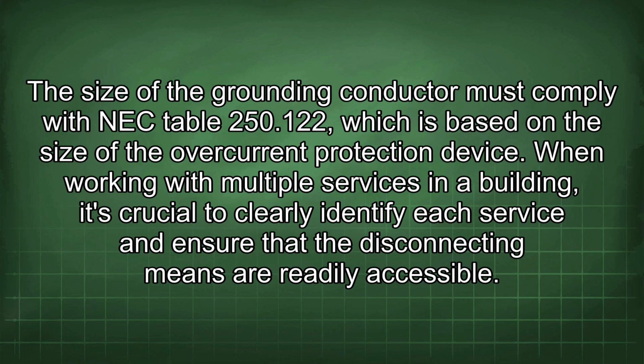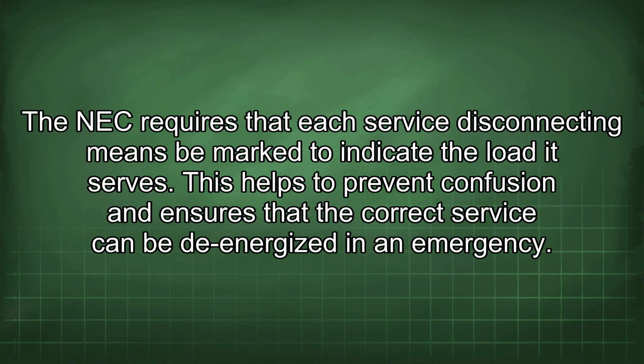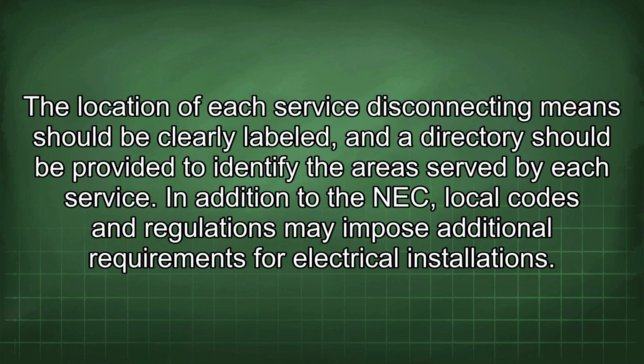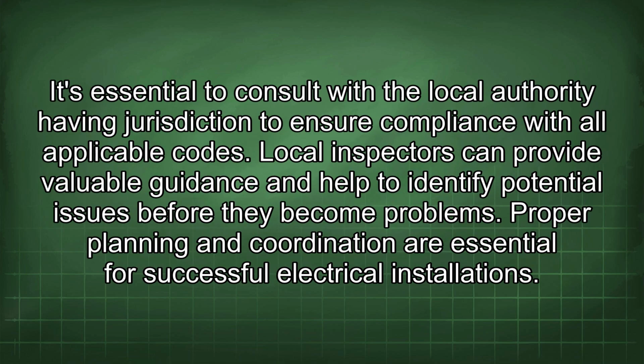When working with multiple services in a building, it's crucial to clearly identify each service and ensure that the disconnecting means are readily accessible. The NEC requires that each service disconnecting means be marked to indicate the load it serves. This helps to prevent confusion and ensures that the correct service can be de-energized in an emergency. The location of each service disconnecting means should be clearly labeled, and a directory should be provided to identify the areas served by each service. In addition to the NEC, local codes and regulations may impose additional requirements for electrical installations. It's essential to consult with the local authority having jurisdiction to ensure compliance with all applicable codes.